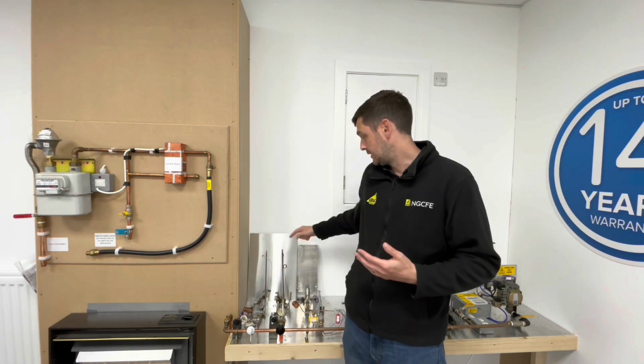We've also got, exactly the same way as we did before, another phial which is located here in the top of the oven, exactly the same way as the one before. Now once the oven gets hot, the vapor inside that phial expands and closes a set of bellows, again allowing a small amount of gas through a bypass to maintain the flame. So let's light this appliance up and see how it goes.